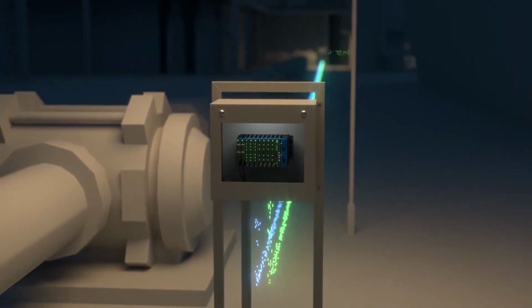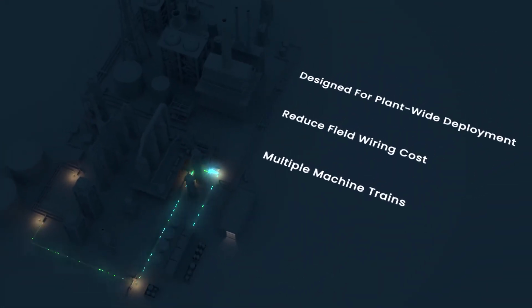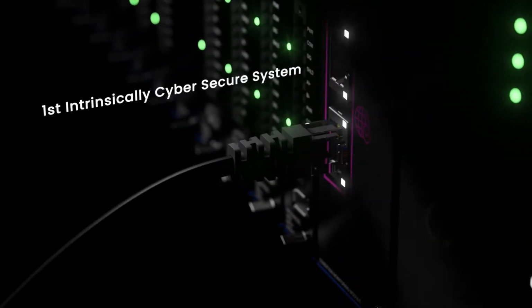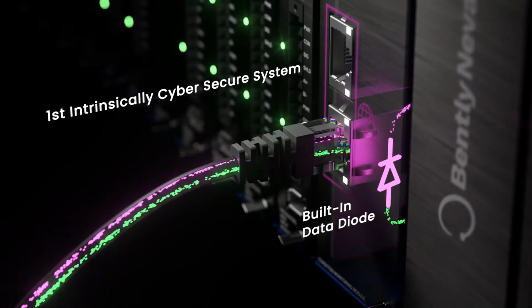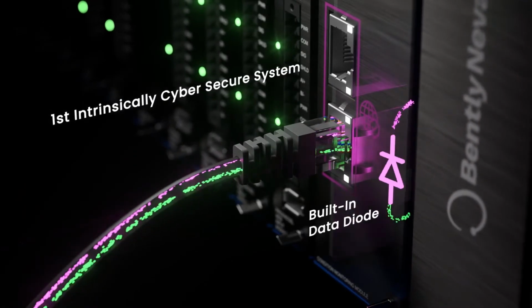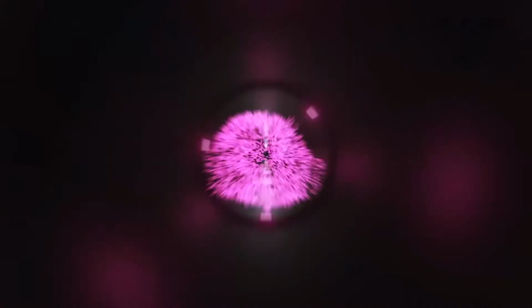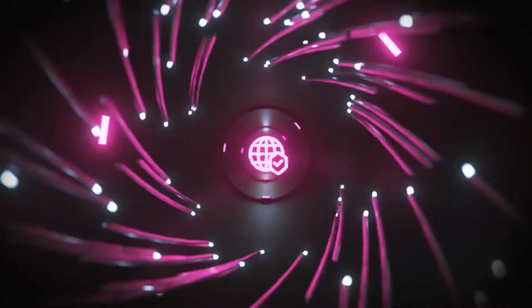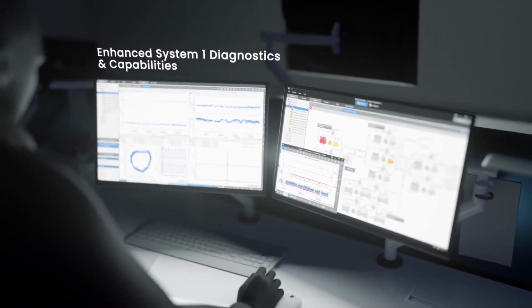There'll be a few new modules that are going to come out specific to that functionality. For the most part, the existing modules coming out this fall will have that functionality added to them to be capable of doing monitoring measurements for those steam turbine applications. Now, you mentioned the acronym TSI, and for people that maybe aren't in the power generation sector, describe that acronym for us. Yeah, turbine supervisory instruments, and it really comes down to steam turbine applicability and how you'd measure those particular assets. Okay, and that functionality is coming in spring of next year then? Yeah, late spring of next year.